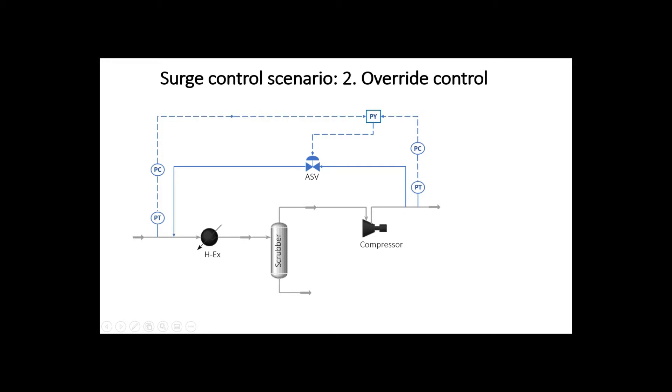In this scenario, there are two controllers at the compressor suction and discharge lines. Here we have two things we're trying to control, but only one manipulated variable: anti-surge flow rate.